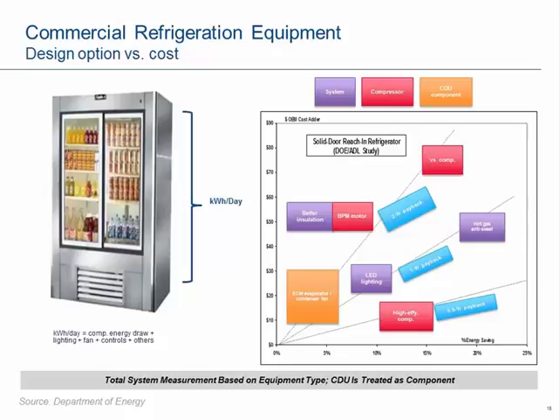Everything within that, the compressor, the lighting, the fans, the controls, every component that consumes energy, anything that comes through the cord, is measured. The unit is tested in a fixed ambient with certain prescribed door openings per the test standard, and then it's certified in the DOE database, which we'll talk about, so the public can see what the energy consumption of that unit is.